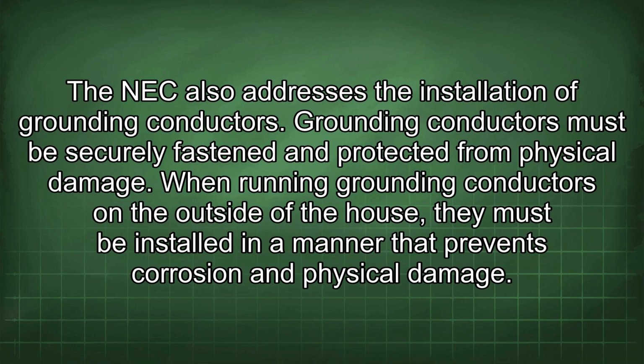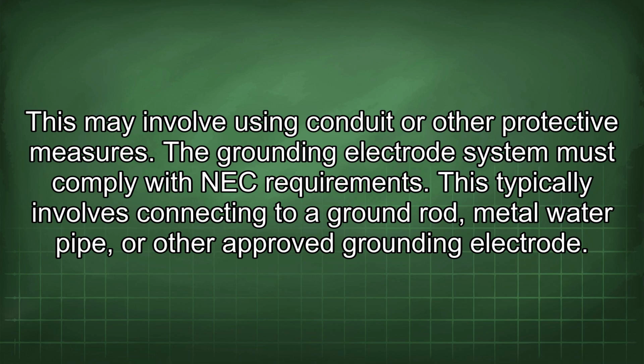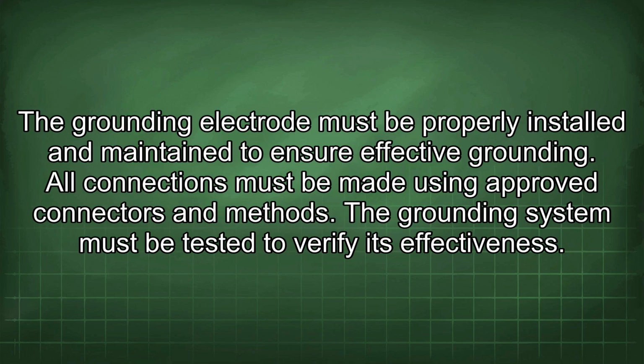The NEC also addresses the installation of grounding conductors. Grounding conductors must be securely fastened and protected from physical damage. When running grounding conductors on the outside of the house, they must be installed in a manner that prevents corrosion and physical damage. This may involve using conduit or other protective measures. The grounding electrode system must comply with NEC requirements. This typically involves connecting to a ground rod, metal water pipe, or other approved grounding electrode. The grounding electrode must be properly installed and maintained to ensure effective grounding.